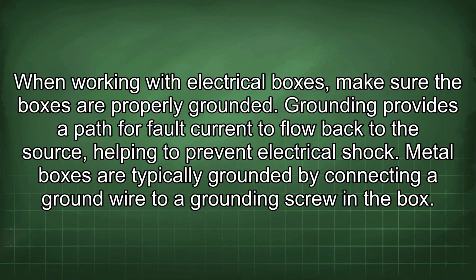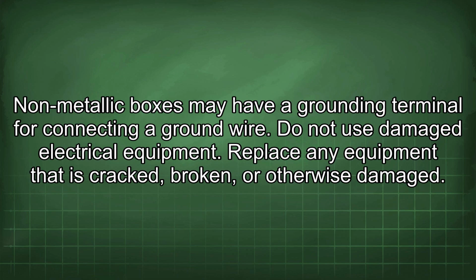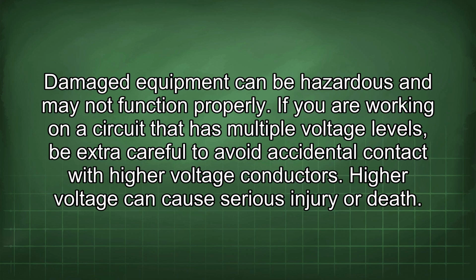When working with electrical boxes, make sure the boxes are properly grounded. Grounding provides a path for fault current to flow back to the source, helping to prevent electrical shock. Metal boxes are typically grounded by connecting a ground wire to a grounding screw in the box. Non-metallic boxes may have a grounding terminal for connecting a ground wire. Do not use damaged electrical equipment. Replace any equipment that is cracked, broken, or otherwise damaged. Damaged equipment can be hazardous and may not function properly.